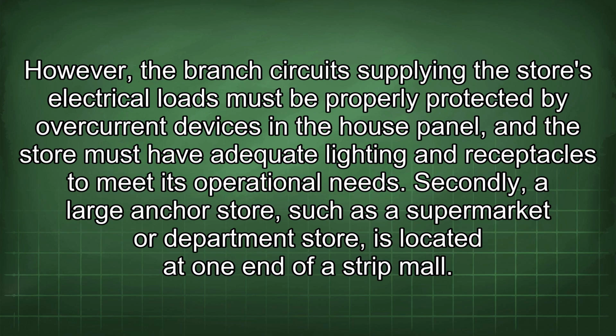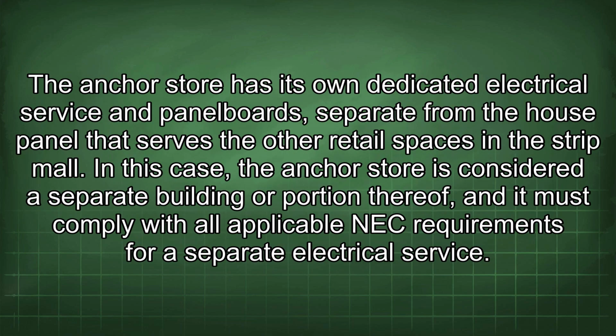Secondly, a large anchor store, such as a supermarket or department store, is located at one end of a strip mall. The anchor store has its own dedicated electrical service and panel boards, separate from the house panel that serves the other retail spaces in the strip mall. In this case, the anchor store is considered a separate building or portion thereof, and it must comply with all applicable NEC requirements for a separate electrical service.